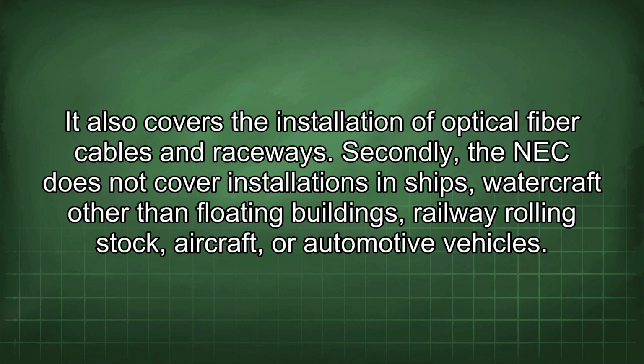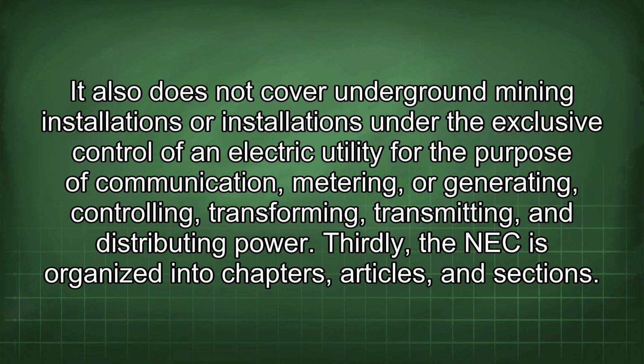Secondly, the NEC does not cover installations in ships, watercraft other than floating buildings, railway rolling stock, aircraft, or automotive vehicles. It also does not cover underground mining installations or installations under the exclusive control of an electric utility for the purpose of communication, metering, or generating, controlling, transforming, transmitting, and distributing power.